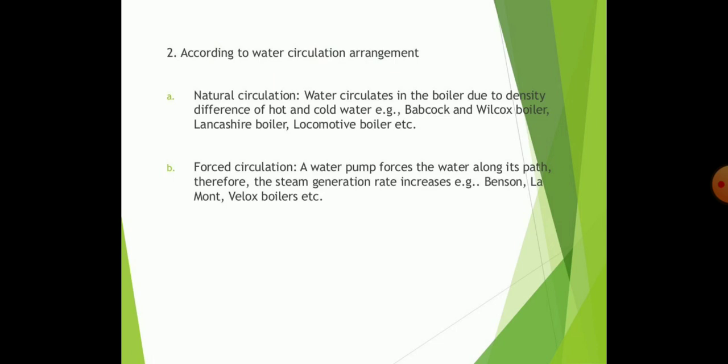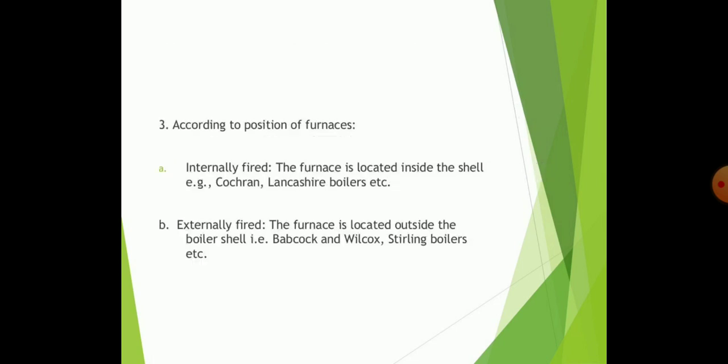These boilers are also classified according to water circulation arrangement. In natural circulation, water circulation in the boiler occurs due to density difference of hot and cold water. Babcock and Wilcox boilers are natural circulation boilers. In forced circulation, a water pump forces the water along its path. Therefore, the steam generation rate increases, as in Benson and Lamont boilers.